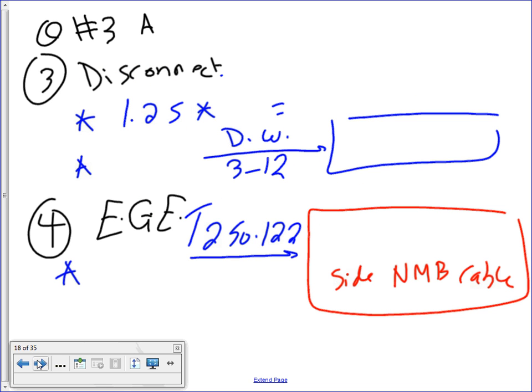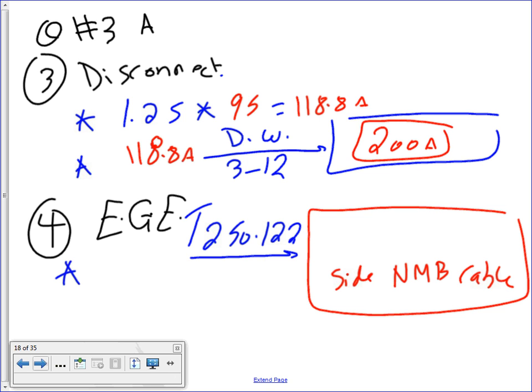Disconnects. For the disconnects, I use the same calculation, guys, 1.25, just to stay consistent. So we got the overcurrent protection device, disconnect, so you can take the 95 here. Again, same calculation, 118.8 amps. 118.8 amps. Take it to the wall, get you a healthy 200 amp disconnect. 200 amp disconnect.